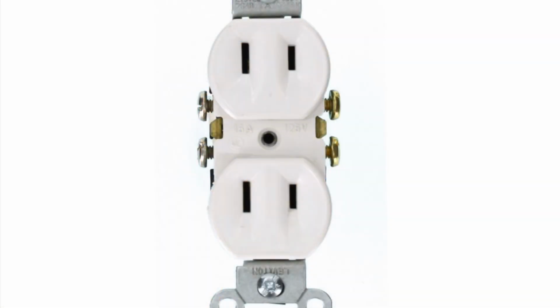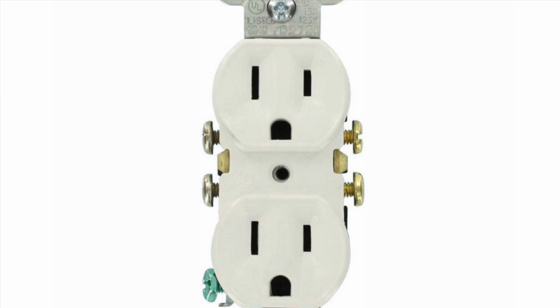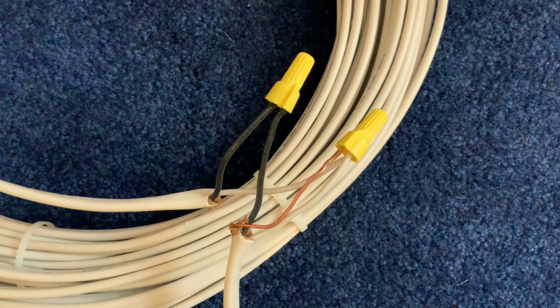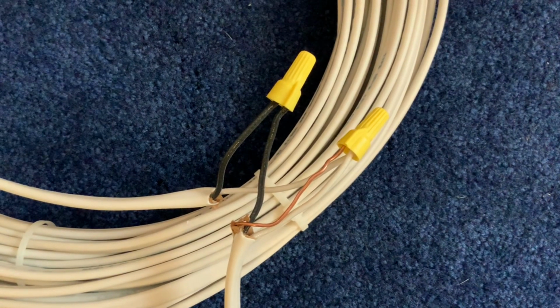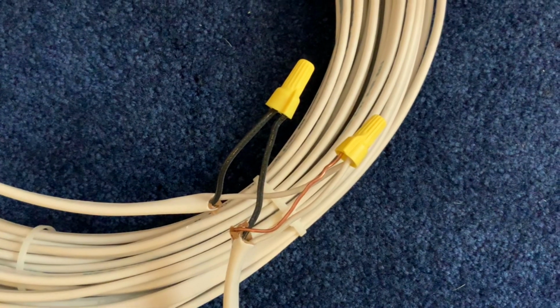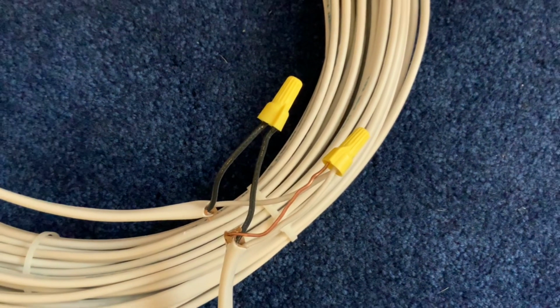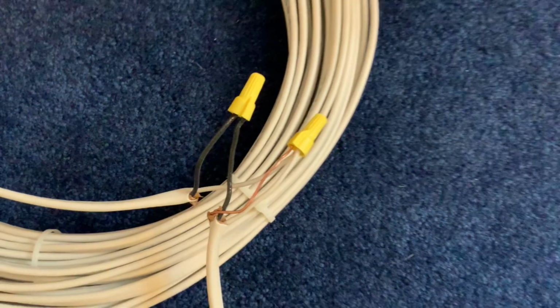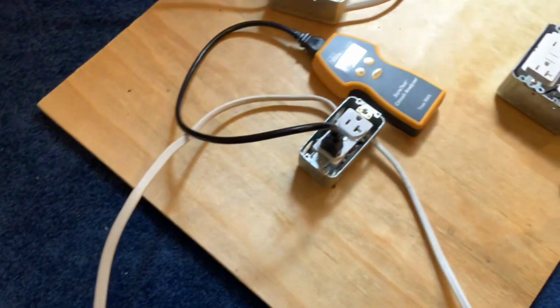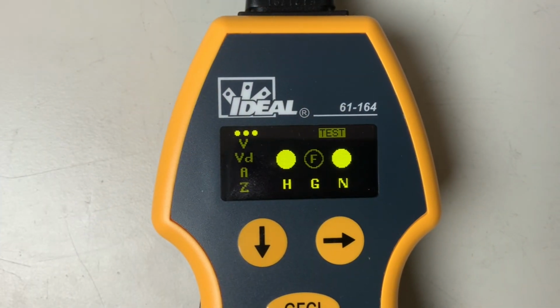A very important feature this unit has is the ability to identify a false or bootleg ground. This occurs when somebody takes an old 2-wire outlet that does not have a ground wire and wants to replace it with a modern grounded outlet, but they don't actually have a ground wire to run to the outlet. So they will take the ground of the new outlet and tie it to the neutral wire of the old wiring. A standard outlet checker will show this as a properly wired outlet, but it is actually a dangerous way to wire these outlets, and this tester will show that it is a false ground by putting an F on the ground lug on the display.